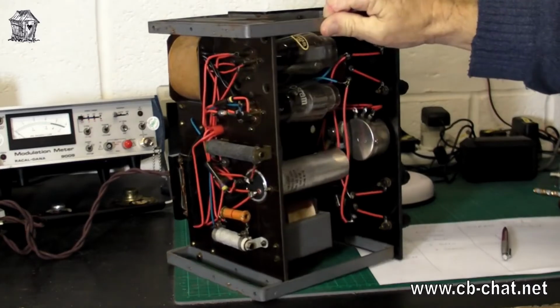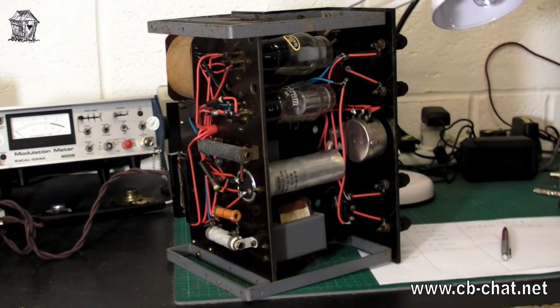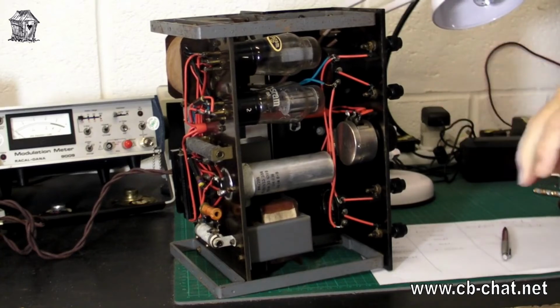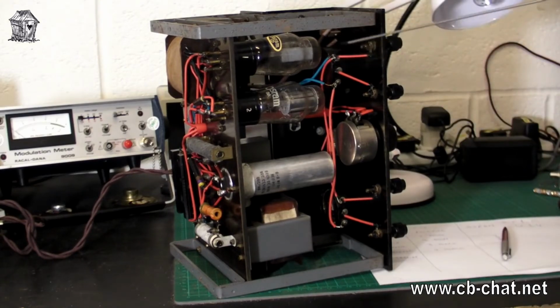And this is a bit stupid. When they designed this and built it, you can't unplug the valves, because if we look here, you've got this potentiometer there, right against the valves. So there's no way of unplugging these valves now if you wanted to replace them. You'd have to strip the unit down quite a lot. I was going to say you'd have to unscrew this front piece, but then there's wires there which are under tension, so you'd have to take the wires off. It'd become a major job just replacing the valves, which doesn't make sense. For old style electrics, you used to always be able to unplug the valve, but not on this.